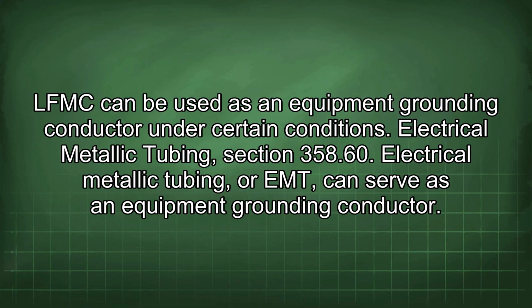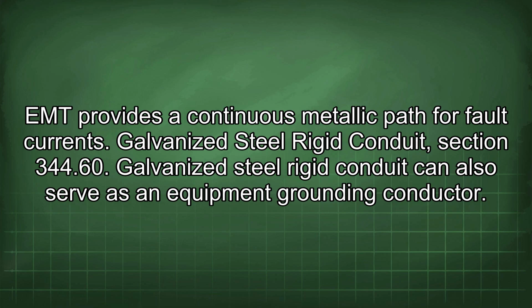Electrical metallic tubing, section 358.60. Electrical metallic tubing, or EMT, can serve as an equipment grounding conductor. EMT provides a continuous metallic path for fault currents.